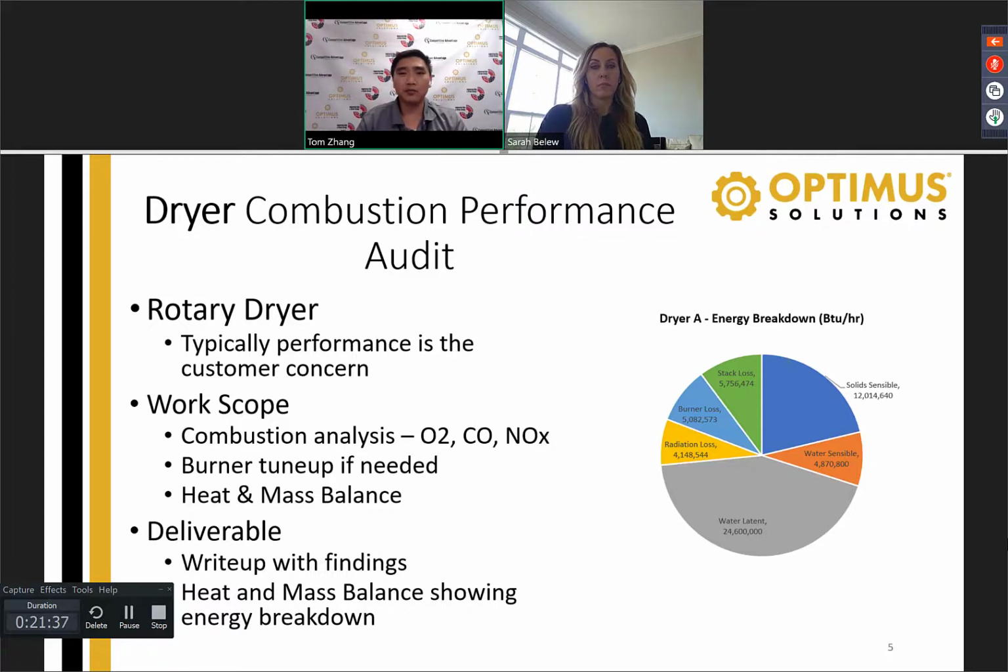Other scenarios are, hey, we're at 200 tons, we want to go to 400 tons. Is that reasonable? It may or may not be reasonable. If it is, what do you need to do to upgrade your burner? What do you need to do to upgrade your baghouse? Do you have enough airflow to go through your system?